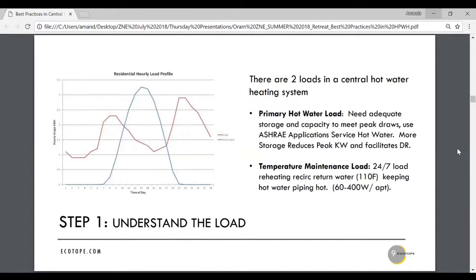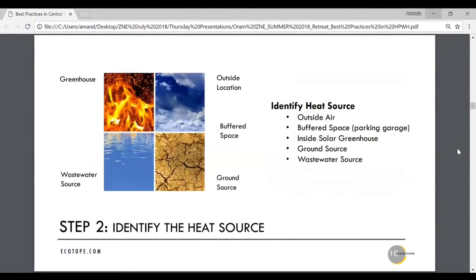That's the key piece, but that's the load on the temperature maintenance. It ends up being about, like we showed earlier, about one-third of the total hot water load, just priming that system. We can't ignore that if we're going to be pushing hot water systems to low EUIs.